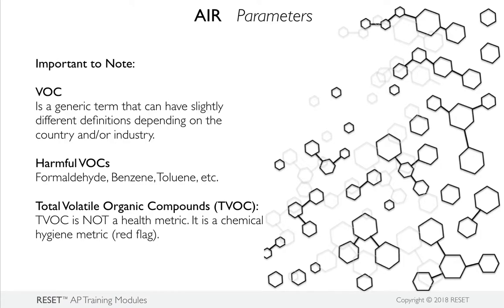And then the TVOC, total volatile organic compound term. TVOC, just to be clear, is not a health metric, but rather it is a way to let me know if I have an interior space that is very high in chemicals or is devoid of chemicals. So think of TVOCs as your total hygiene metric. And if your TVOCs are very high, maybe you need to come in because it's a bit of a red flag that your space is full of chemicals and you need to do a little bit of detective work or diagnostic work.